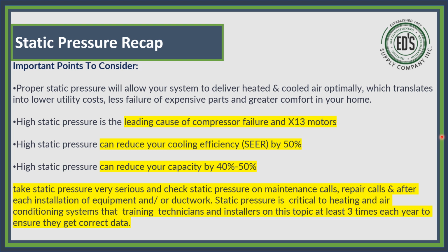I have seen a house, brand new house, everything was built brand new. They put a 2-ton unit in because they needed 800 CFMs. So they put a 2-ton furnace in, set everything up, left it. Never checked anything else. The homeowner was very aggravated because during the heating season, the unit would not keep up. The unit ran all day long. It wouldn't get hot enough in the house, and they were complaining about it.